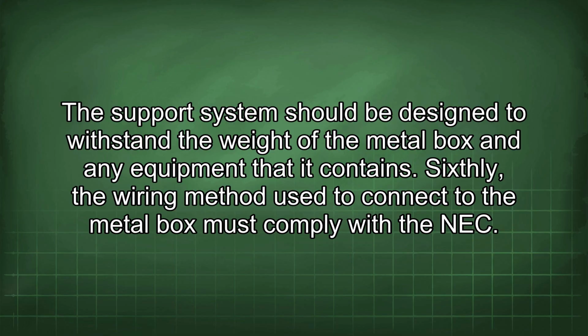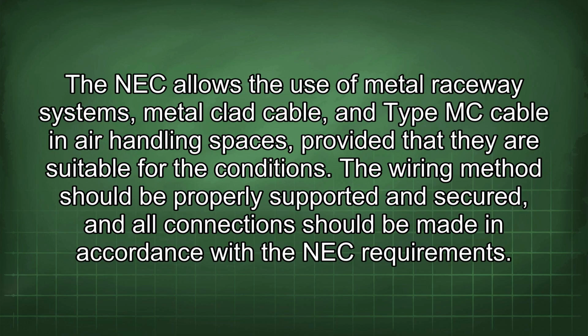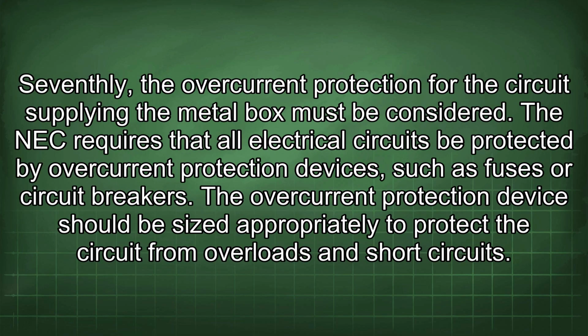Sixthly, the wiring method used to connect to the metal box must comply with the NEC. The NEC allows the use of metal raceway systems, metal clad cable, and Type MC cable in air handling spaces, provided that they are suitable for the conditions. The wiring method should be properly supported and secured, and all connections should be made in accordance with the NEC requirements. Seventhly, the overcurrent protection for the circuit supplying the metal box must be considered.